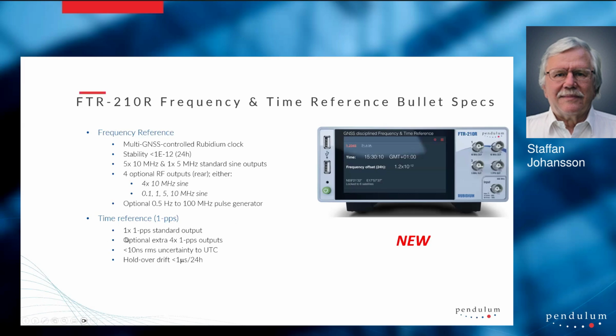As a time reference, that means providing a 1 PPS that is more or less synchronous with Coordinated Universal Time, UTC. We have 1 standard output on the front, and on the rear we have 4 extra optional 1 PPS outputs. The uncertainty to UTC is better than 10 nanoseconds RMS, which is a very good value, and the holdover drift, if you lose GNSS contact, is better than 1 microsecond over a full day, over 24 hours. So these are the frequency reference and time reference bullets.